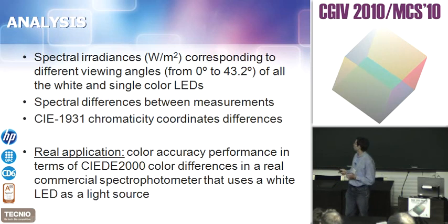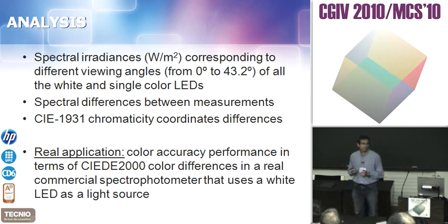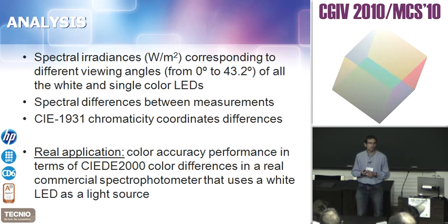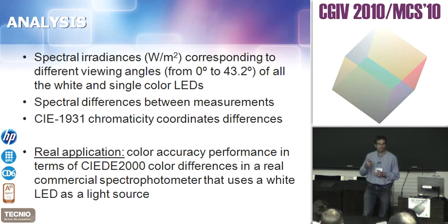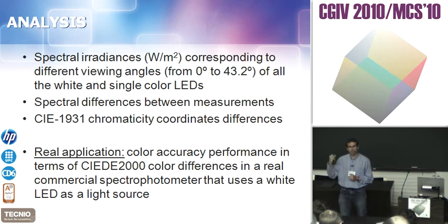Which analyses did we perform? First, we measured the irradiance — watts per square meter — at all viewing angles from 0 to 43.2 degrees, for all white and color LEDs. Then we calculated the spectral differences of all measurements, and also the chromaticity coordinate differences for the white LEDs. Finally, since spectrophotometers using white LEDs as light sources have appeared on the market in the last four years, we analyzed one such device to see if what we found with light sources also affects real spectrophotometers you can buy.